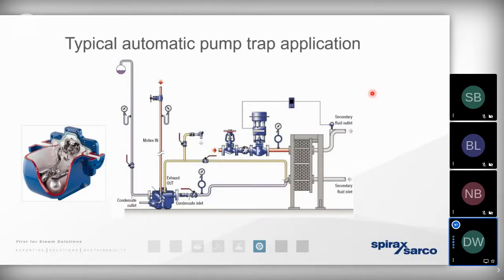And basically that means that when there is a good motive steam energy, then it will operate in exactly the same way as a float trap. But when we don't have any steam pressure available, we can simply call for a very, very small mass of high pressure steam. And that exists just before the steam is reduced in pressure across the pressure reducing valve or control valve. So by lending that high pressure motive steam, it enables us to shunt the condensate away from the process. So two benefits, really.